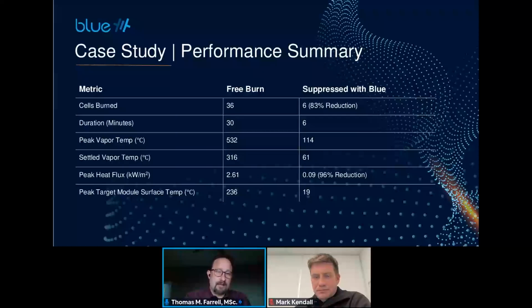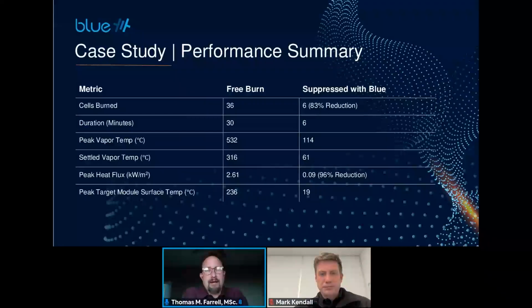That's well within the normal operating temperature for one of those batteries, unless it was experiencing a similar type of electrical failure, if that was coming from a power grid spike or a BMS system failure that caused overcharging of everything in the rack. This module that was under fire was managed to a level that it would not have caused thermal runaway in the module above. It's a very positive result in that regard.